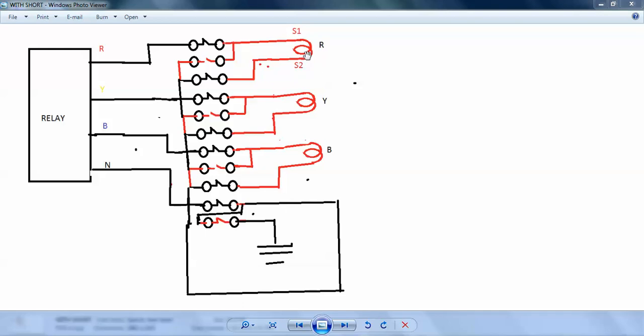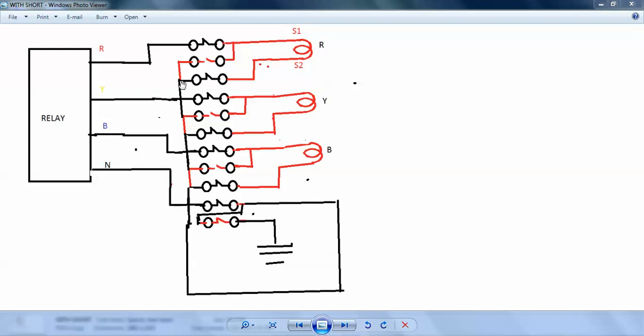And further, how the current flows in normal case, then after how the current flows in shorting case. So normally when the feeder is energized, the current flow goes through S1 to the relay and back to neutral. You can see the path through this way, so R phase current flows like this through R and neutral back to this way, and coming to this path. So current flow is normal. R is like Y and B phase, like here flow like this and coming back to the neutral.